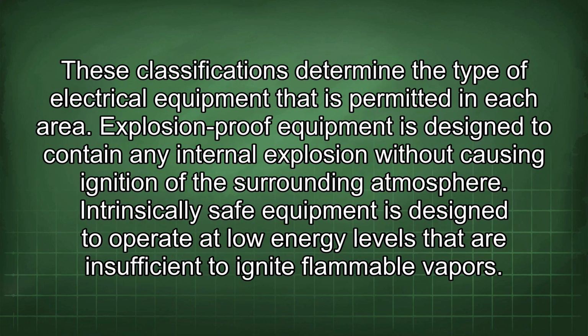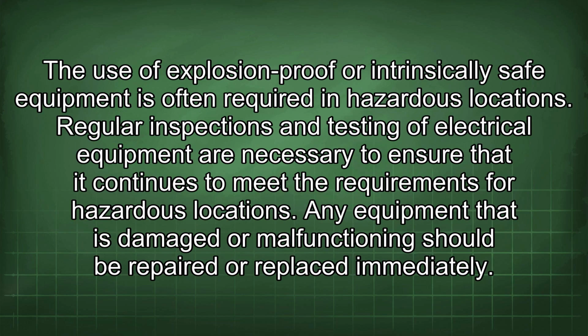These classifications determine the type of electrical equipment that is permitted in each area. Explosion-proof equipment is designed to contain any internal explosion without causing ignition of the surrounding atmosphere. Intrinsically safe equipment is designed to operate at low energy levels that are insufficient to ignite flammable vapors. The use of explosion-proof or intrinsically safe equipment is often required in hazardous locations.